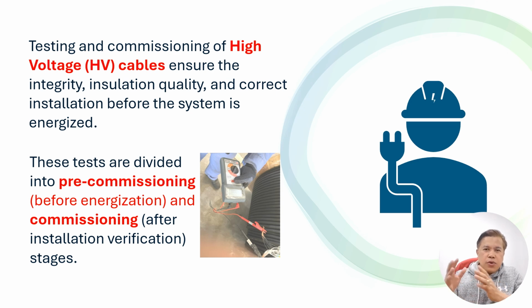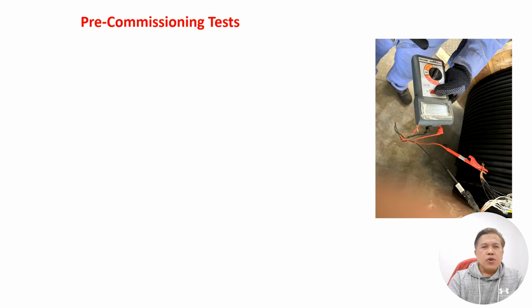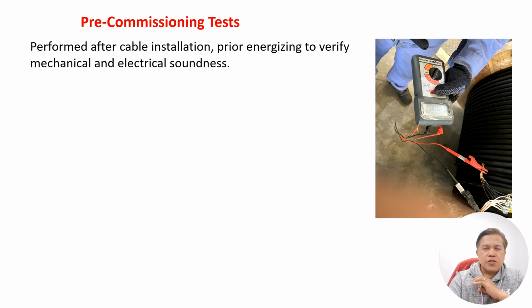All right. So the cables coming from the manufacturer are to be tested. All of those tests have been carried out, and then after arrival, our cables need to be tested as well. So what is the pre-com test?